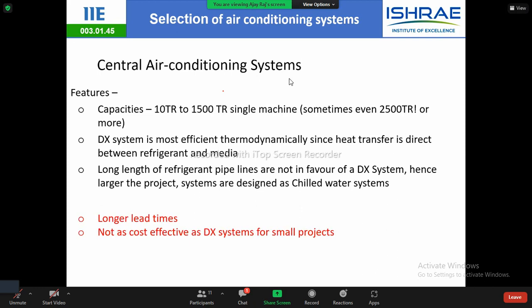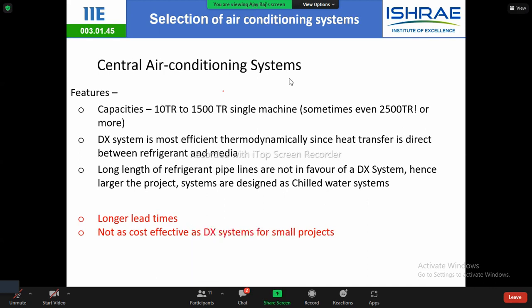For water cooled chillers. If you want to go with air cooled, that is still okay, anything above 60 or 80 tons. Features, capacities: you can have a chilled water system right from 10 TR to 1500 TR single machines, or sometimes it goes to 2500 TR also, 3000 TR also. DX system is most efficient thermodynamically since heat transfer is direct between the refrigerant and media. Long lengths of refrigerant pipes are not in favor of DX system, hence large project systems are designed with chilled water system. Longer lead times, not as cost effective as DX system for small projects.